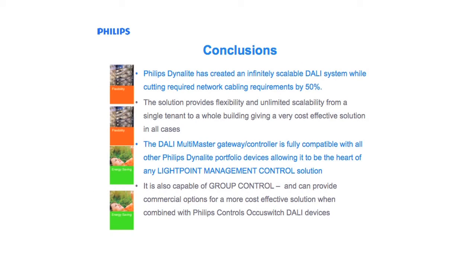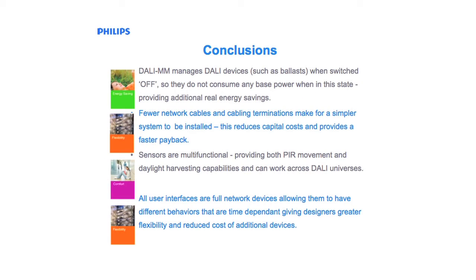So in conclusion, we can see that the Philips Dynalite DALI MultiMaster solution has reduced network cabling by 50%. The solution provides a flexible and unlimited scalability from a single tenant to an entire building while maintaining the advantages of a DALI system. The DALI MultiMaster gateway controller is fully compatible with all other Philips Dynalite devices, allowing all other solutions, integrations, user interfaces and load controllers available for various other solutions as required. Built into the DALI controller is a 20A power relay capable of removing the standby current consumption when all the lamps have been switched to off. Fewer network cabling and fewer cable terminations make for a simpler system to install, reducing not only cable costs but labour costs, producing a faster payback.